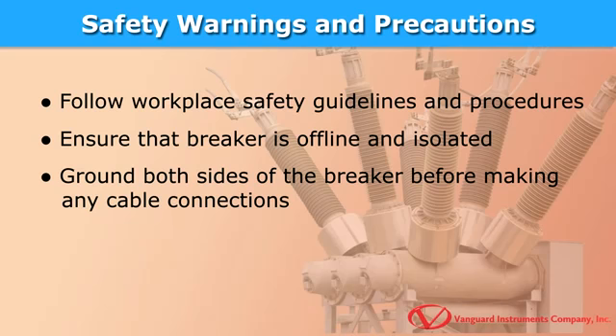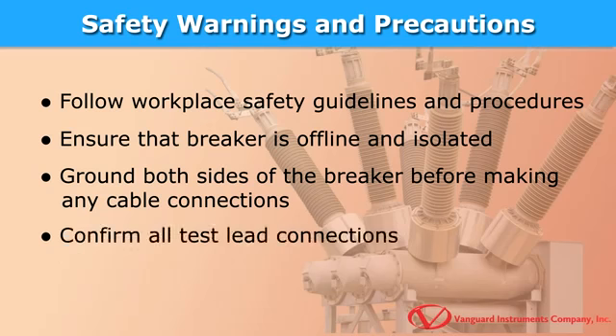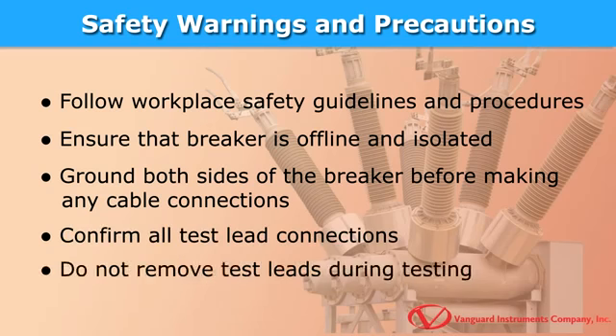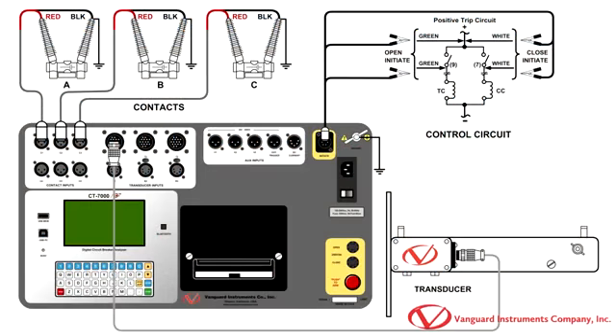For operator safety, we recommend grounding both sides of the breaker before making any cable connections. Confirm that all cables are connected properly. Lastly, do not remove any test leads during testing. We'll be making cable connections per the connection diagram shown here.